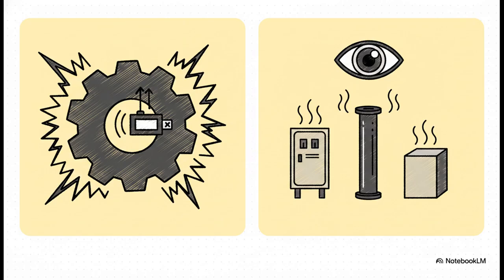Vibration sensors measure mechanical motion. They need one-to-one physical contact, and they only work on rotating machinery. Thermal monitoring, on the other hand, measures heat. It provides zone-wide coverage, and it covers non-rotating and electrical equipment too. A vibration sensor literally cannot detect a smoldering ember in the dust extraction system. It won't spot a stuck board causing friction or an electrical panel that's about to arc. Why? Because fire isn't a vibration problem, it's a heat problem.